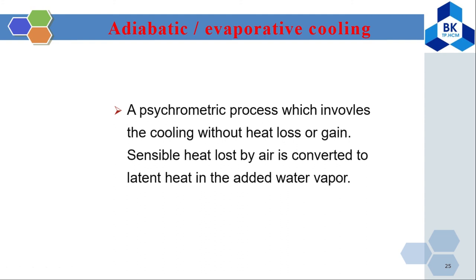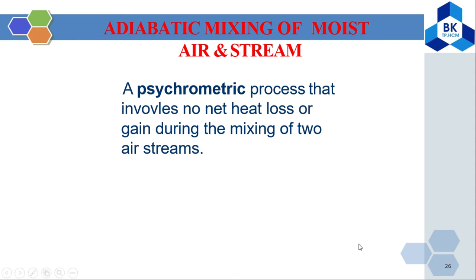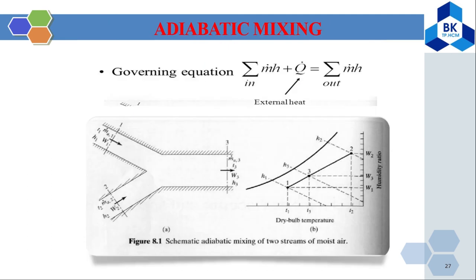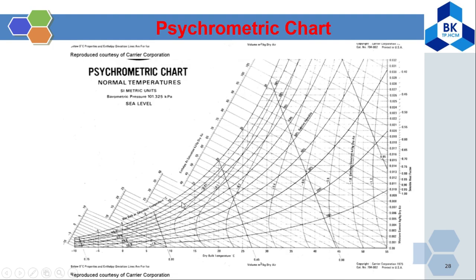Adiabatic or evaporative cooling is a psychrometric process involving cooling without net heat loss or gain — the sensible heat lost by the air is converted to latent heat in the added water vapor. Adiabatic mixing of moist air streams is a psychrometric process involving no net heat loss or gain during the mixing of two air streams, governed by the equation: total (ṁh) + q̇ = total outlet (ṁh), where q̇ is the external heat added to the mixing process.